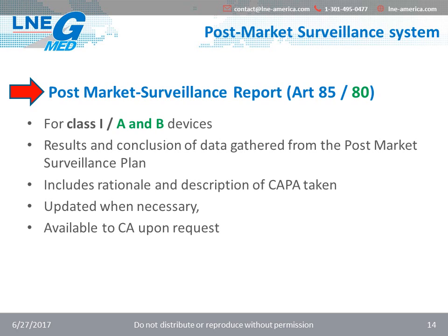This report shall be updated as necessary, with no frequency requirement in the article itself, and made available to the competent authorities upon request. Here there is a slight difference between the IVDR and the MDR. As for the IVDs, this report shall also be available to the notified body upon request.